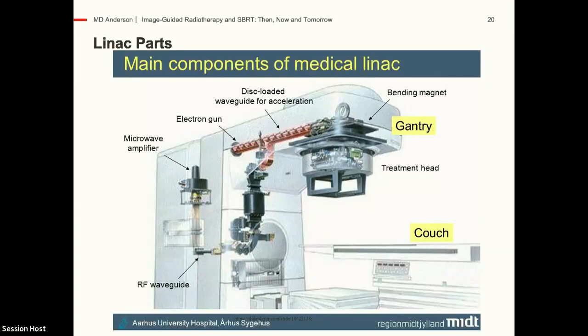The foundation of it includes a waveguide and a microwave amplifier that amplifies the beam from the electron gun and shoots it down through the accelerator waveguide. That hits the actual target, turning it into a photon beam, or there's no target, just a scattering foil, which allows an electron beam to penetrate past and be shaped by the machinery in the treatment head, including multi-leaf collimators and wedges, and a whole plethora of devices, all meant to make sure that beam is shaped uniquely to the shape of the target you ultimately want to treat.